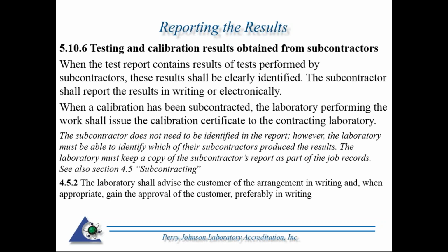Okay, 5.10.6, this is in regards to subcontractors. So this is if you're subcontracting your calibration or testing and you're incorporating that into the reports that you provide your clients. So when the test report contains results performed by subcontractors, these results shall be clearly identified. The subcontractor shall report the result in writing or electronically.